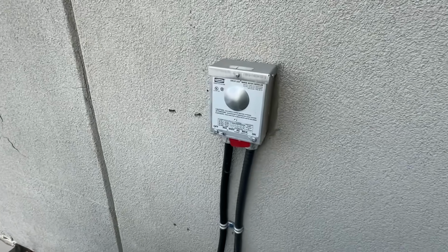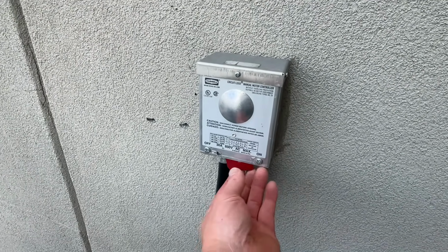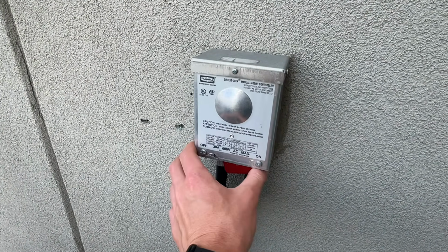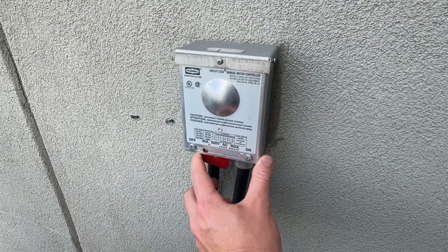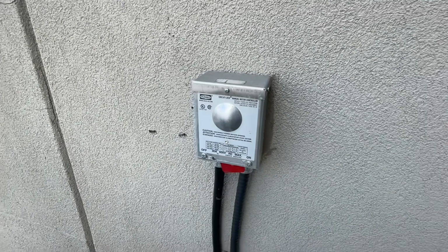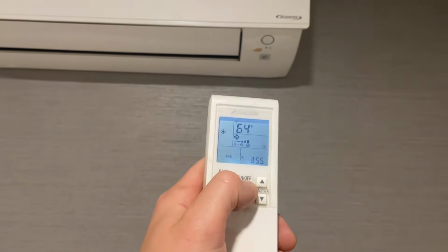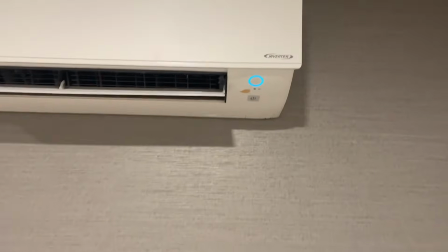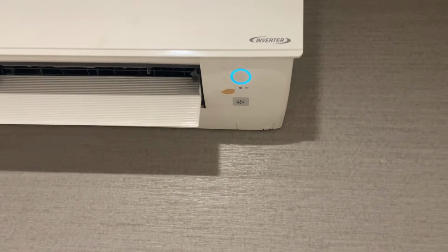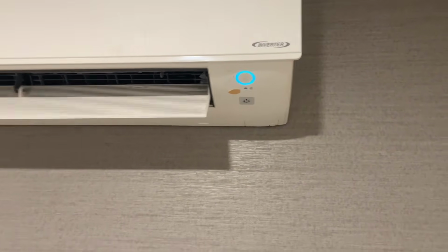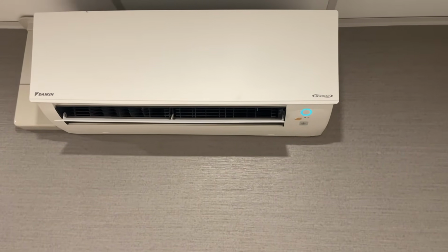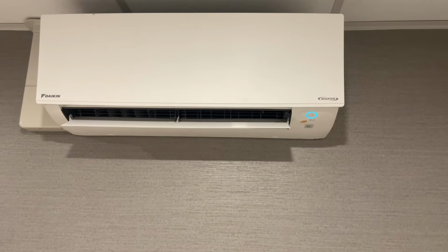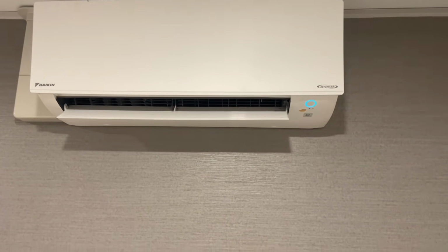And then our next step on our flow chart is to actually cycle power. So you guys can do this from a disconnect outside or a breaker in your house if you know where it is. So we're gonna shut the power off, fire it back on, and we'll go check our indoor unit. Okay, we're back in our space now. Let's turn the power on with our remote. And that appears to have cleared our flashing error light on our unit. So we're gonna sit around, make sure this thing comes on, and we'll go outside, check our refrigerant levels, running pressures, and we'll check our voltage too, just to be safe.